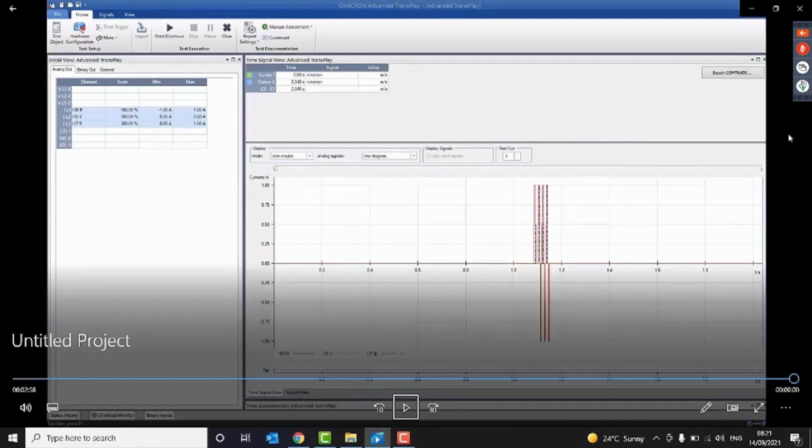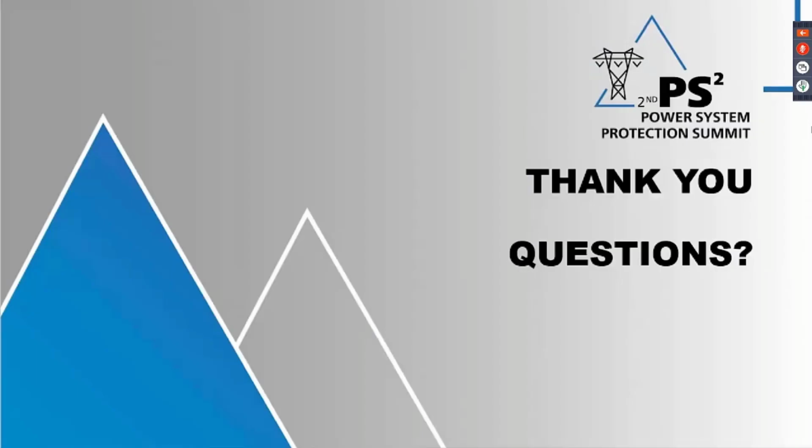So in this way, we can make a simulation of the fault that we studied through MATLAB Simulink, and simulate it by real injection using the CMC356 test kit, with the advanced test module offered by Test Universe 4.3. Thank you all, and we are ready now for your questions.